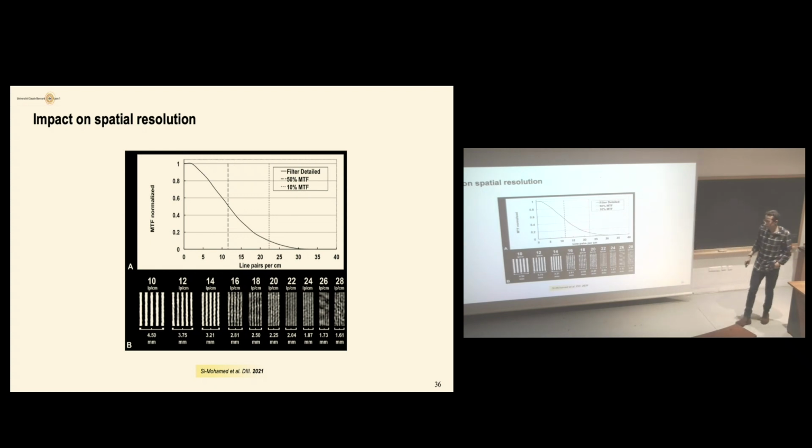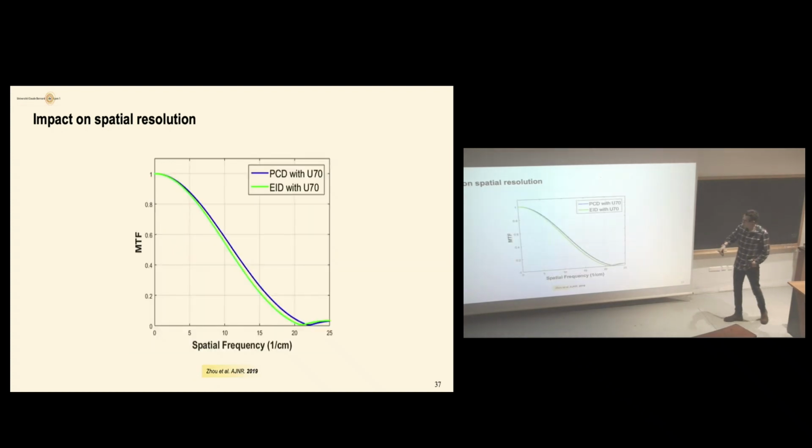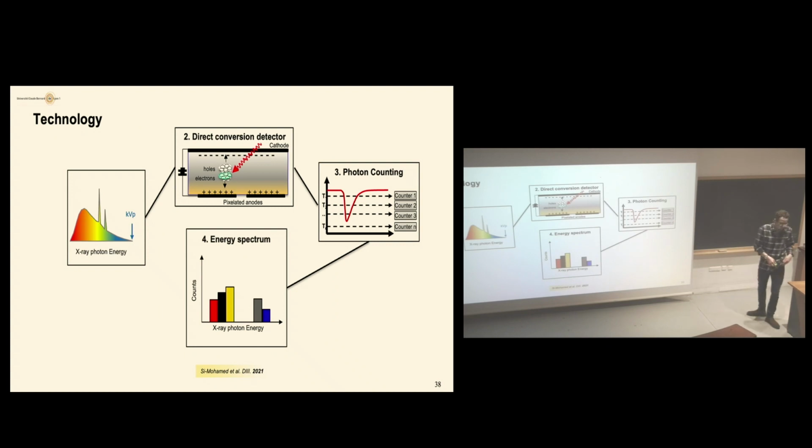So it's 2 to 3 times even more than conventional CT. Here it's a Siemens system back in 2019 with a different setup, and also the cutoff of photon counting CT is improved. Okay, so spatial resolution, it's a huge, huge advantage, and I will say that it is an incremental advantage. It's not disruptive or groundbreaking. Now we're going to talk about the most important and interesting part. It is the groundbreaking aspect of these detectors.